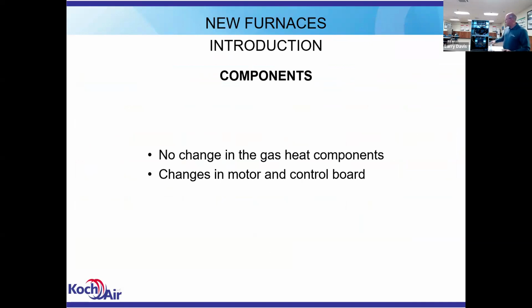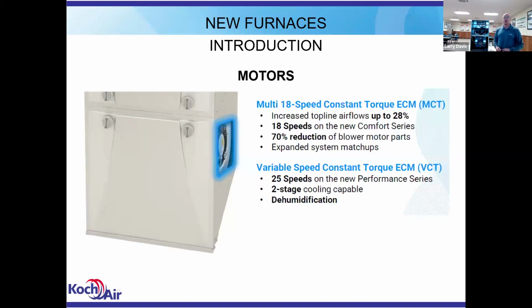So components, what's changed? Everything from this blower shelf up is the same as it was in the previous model. Didn't make any changes in the gas heating section. What's changed is from here down, it's the blower motor and the control board. Those are the changes that were made to gain that efficiency. And again, for the baseline or the entry level furnaces, it's an 18-speed motor, and it's a constant torque, so you'll select a speed and it'll run at that. For the mid-tier and high tier, it's a 25-speed. They are two-stage cooling compatible, and they have the dehumidification capability.